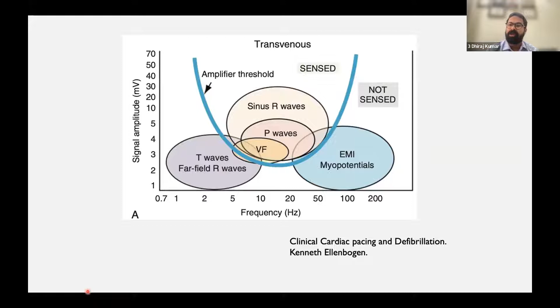Again, on the other end of the spectrum, anything which is less than 2 hertz is generally thought of as non-physiological, or a physiological signal which we don't want to treat, like a T wave or a far field R wave. Correct? And so is the case with amplitude. Anything with an amplitude less than 3 millivolts and not falling into this range, we think of as non-physiological signals. This is very important for the device to not give therapies for non-physiological signals or physiological signals which we don't want to treat.